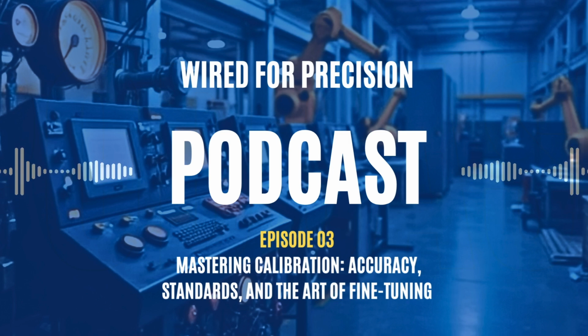Calibrating in the lab is one thing, doing it out in the field is another. Here are some of the real-world challenges that technicians and engineers face during field calibration. 1. Accessibility issues. Instruments are often installed in hard-to-reach or hazardous locations, at height, in tight spaces, or within live systems that can't be shut down easily. Second, limited downtime windows. Production rarely stops just for calibration. Engineers are often under time pressure, especially in plants running 24/7. That means calibrating quickly, efficiently, and without causing delays.